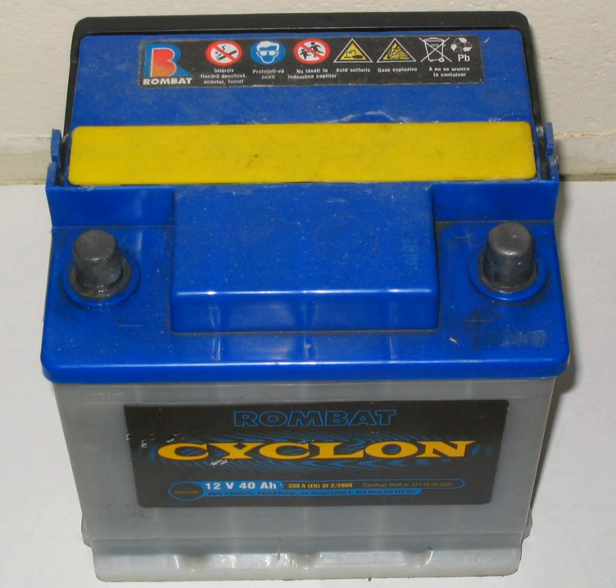However, because tubes and cylinders have less active material in the same volume, they also have a lower energy density than flat plate cells, and less material available to shed before the cell becomes unusable. Tubular, cylindrical electrodes are also more complicated to manufacture uniformly, which tends to make them more expensive. These trade-offs limit the range of applications to situations where there is insufficient space to install higher capacity flat plate units.